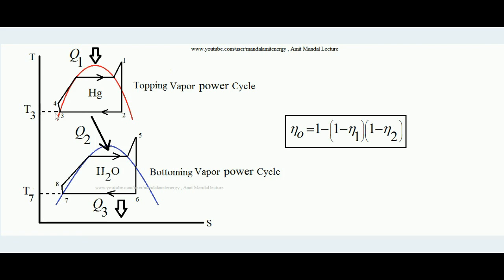Mercury loses heat between points 2 and 3, for example at 350°C. The bottoming vapor cycle uses water as the working fluid. Water enters the boiler at point 8 and comes out in superheated form at point 5, then expands in the turbine to point 6, and condenses between points 6 and 7. Since the boiler requires heat and mercury is losing heat at a higher temperature, that rejected heat is utilized to heat the water and convert it into superheated steam.